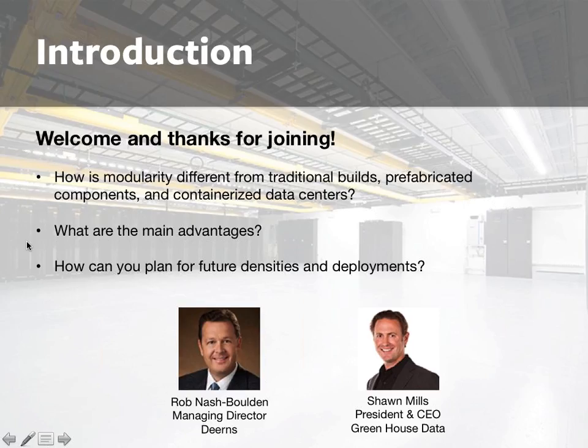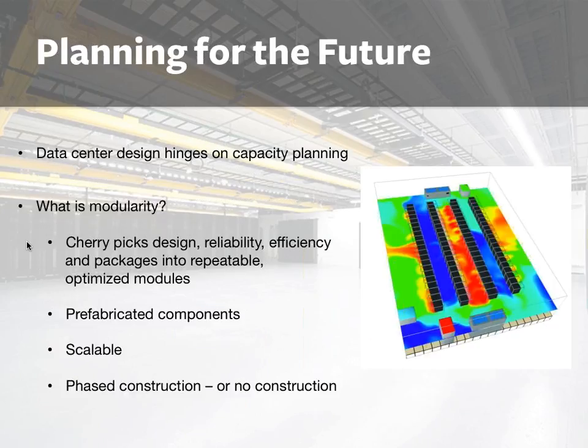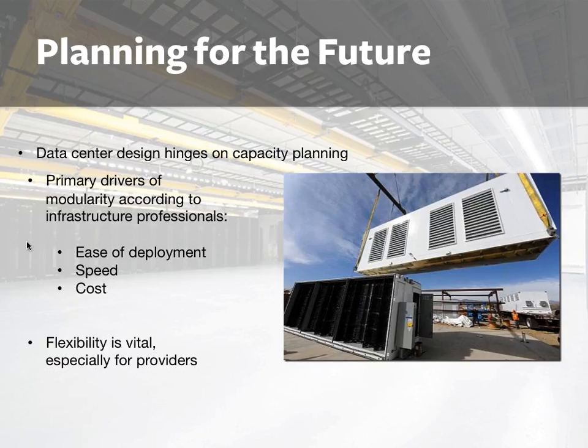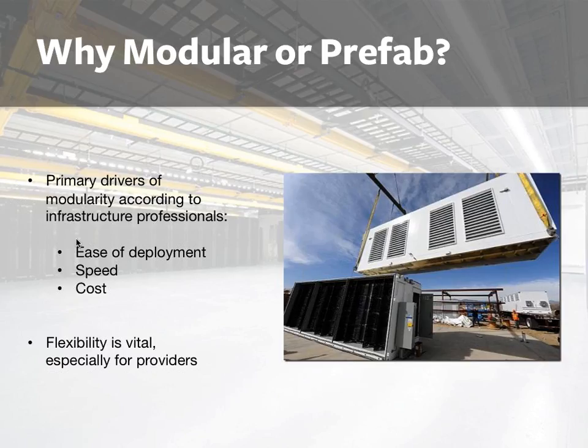As we were planning for the future — really an unknown future — for our data center design, we had to take a lot of different components and challenges into mind. We looked at all of the various options, from containerized data centers to stick-built to prefabricated. From a service provider's perspective, flexibility is critical for data center design. We needed to figure out how to maximize flexibility for potential clients that could be anywhere from 1kW of load in a cabinet to 12kW or higher. Being able to scale quickly up, down, and move loads around the data center floor was really important.